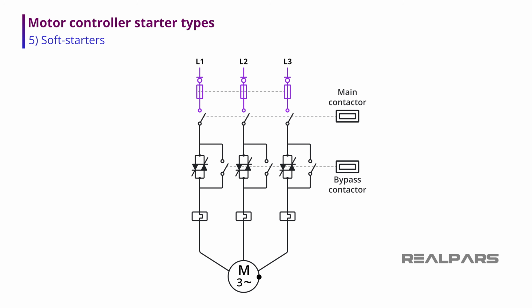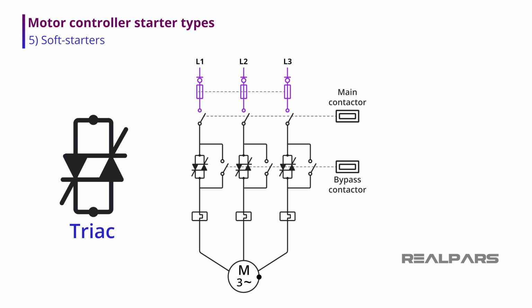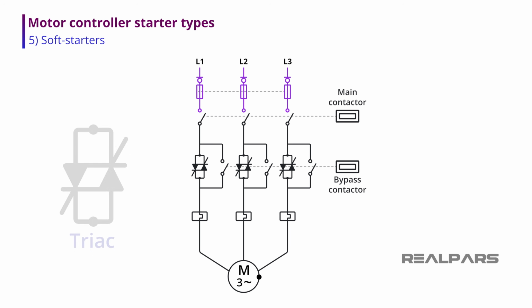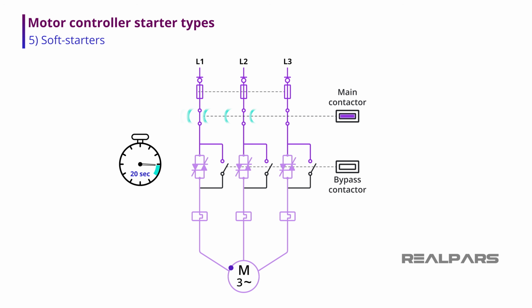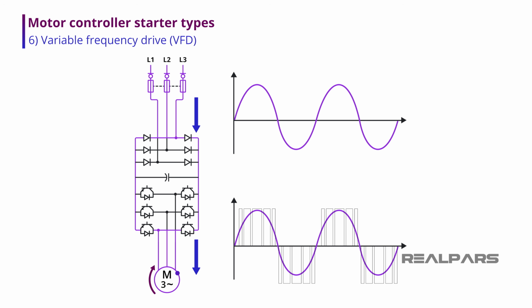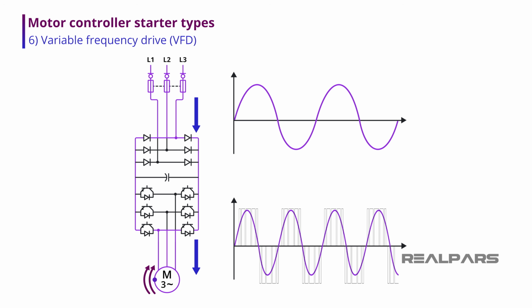Soft starters are another method used for limiting starting current. Soft starters use solid-state electronics to limit the startup voltage and current. With a soft starter, the voltage is gradually increased during motor startup. This allows the motor to slowly accelerate and gain speed in a controlled fashion. A variable frequency drive, or VFD, is similar to a soft starter, but allows the speed of the motor to be varied by varying the frequency of the output to the motor. Because the voltage is also regulated in the process, the startup current is also reduced with the use of a VFD.